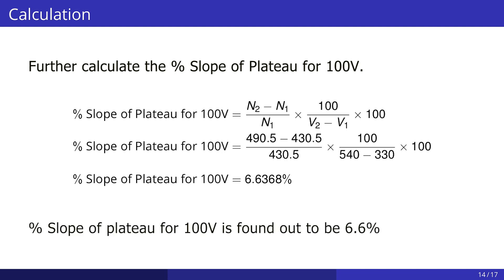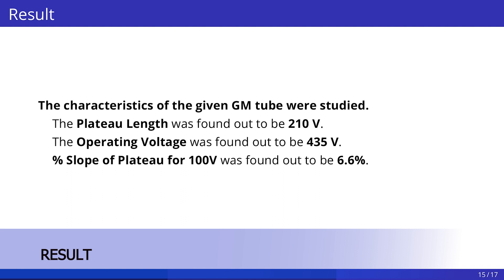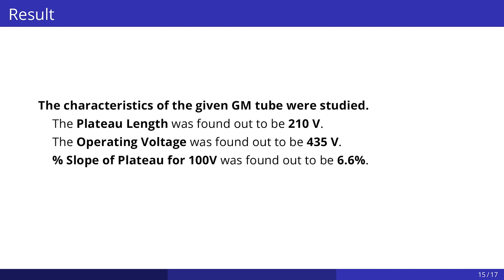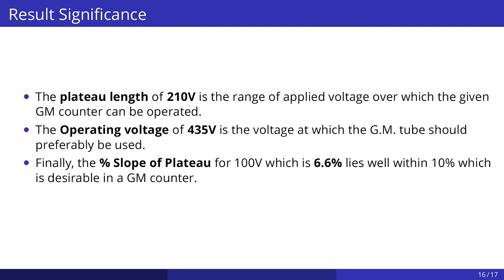By calculating, we have found the percentage slope of the plateau for 100 volts to be 6.6%. The significance of our result is that the plateau length of 210 volts is the range of applied voltage over which the given GM counter can be operated. The operating voltage of 435 volts is the voltage at which the given GM counter should preferably be used. Finally, the percentage slope of the plateau for 100 volts — which is 6.6% for the given GM counter — lies well within 10%, which is desirable in a GM counter.